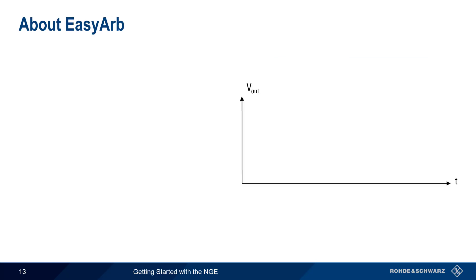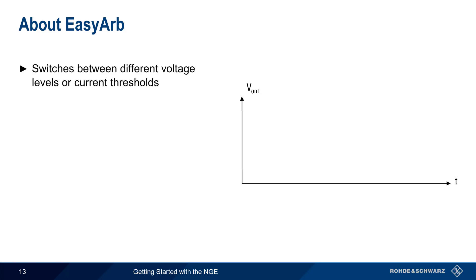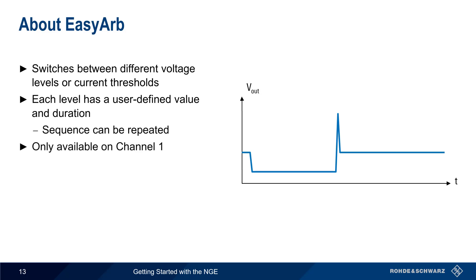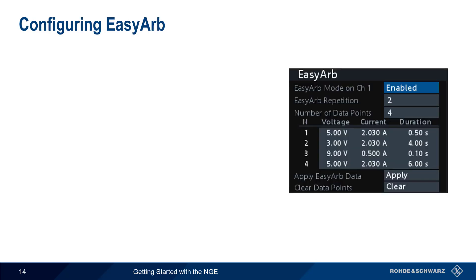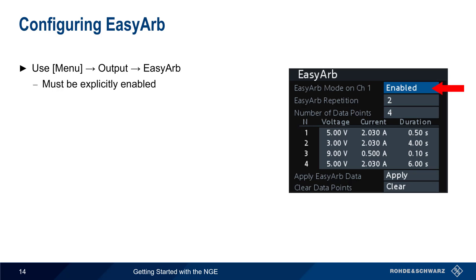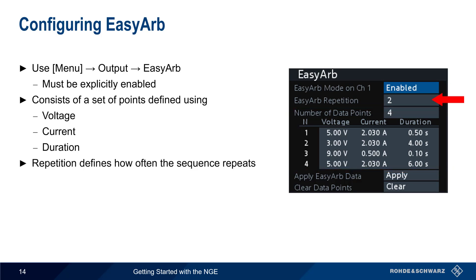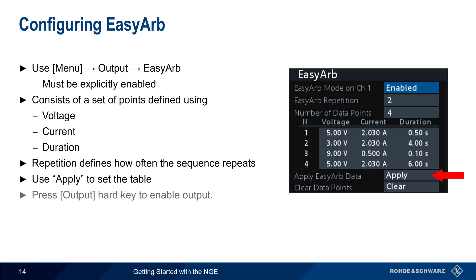Unlike EasyRamp, which linearly increases the voltage from zero to a defined value, EasyArb switches the NGE output between different discrete voltage levels or current thresholds. Each level has a user-defined value and duration, and this sequence can be repeated multiple times. Note that EasyArb is only available on Channel 1. To configure EasyArb, press the menu hard key and then select Output EasyArb. Note that this function must be explicitly enabled. The EasyArb sequence consists of a series of points, each defined as a voltage, current, and duration. Once you're finished configuring these values, use Apply to set the table. On the NGE front panel, press the Output hard key to enable output, and then Enter to start the sequence.